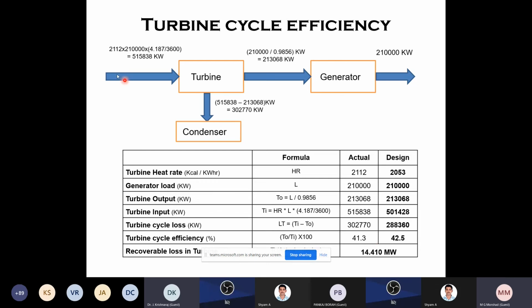You will not find this anywhere in the books. It was established by me during my energy audit. It is not available there. So you can see the actual efficiency is 41% and the design is 42%. Though these are somewhat conservative values, normally it should be 38 to 39. But the design value also is around 41, so some discrepancies are there. From these differences, you can say we are losing around 15 megawatts in the system. This is called the turbine cycle efficiency. This is for academic purposes; you can establish it and think it through.